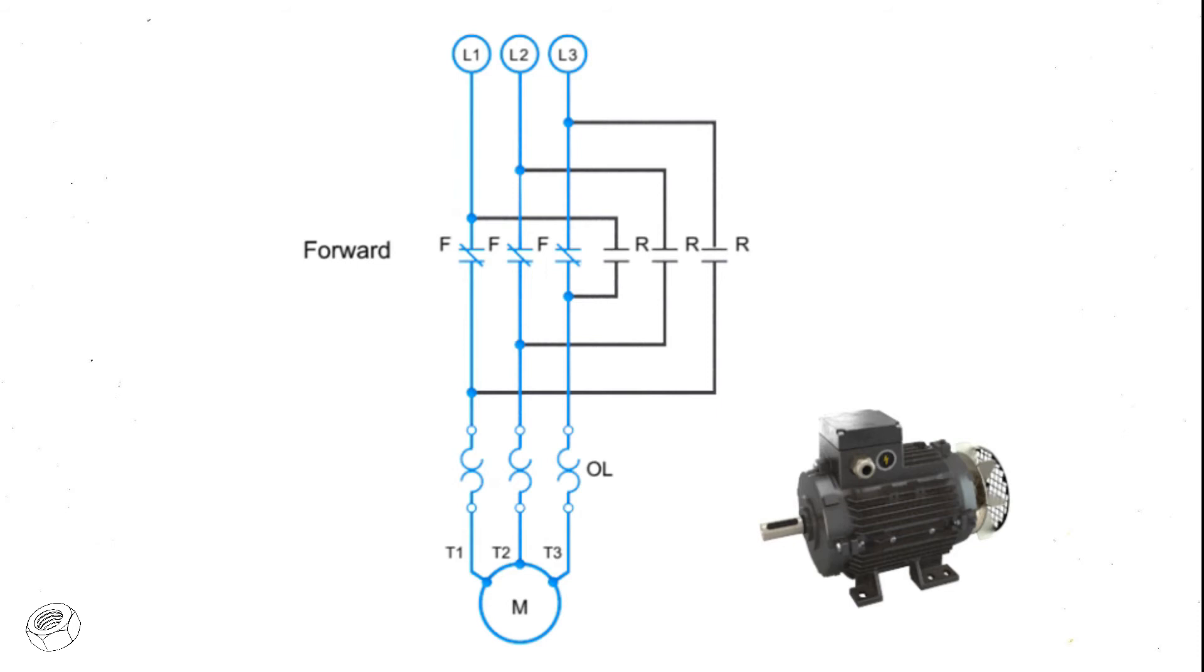To run the motor in reverse then, two of the contacts must be switched. In this case, L1 is connected to T3, and L3 is connected to T1. L2 and T2 remain connected.